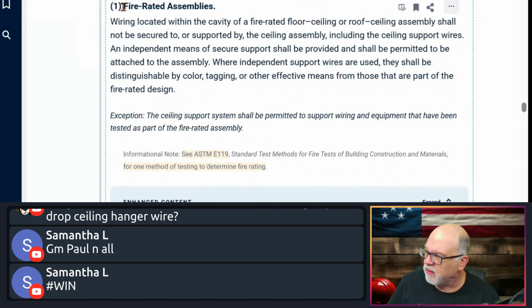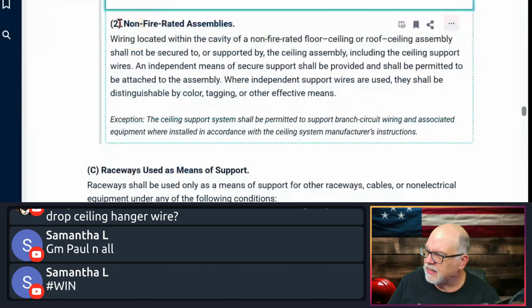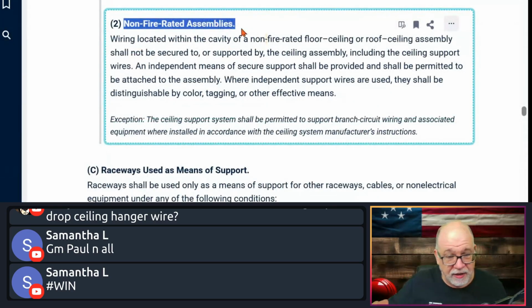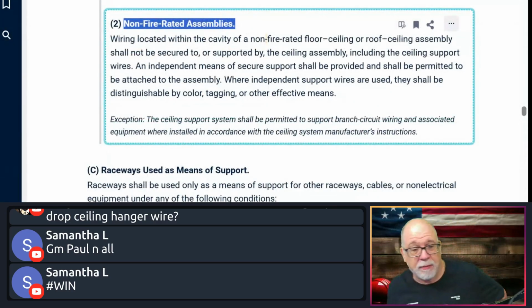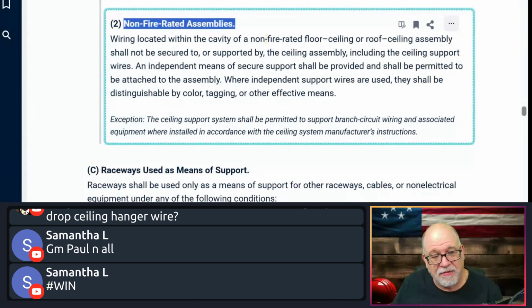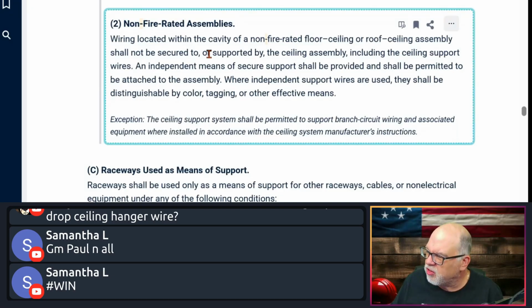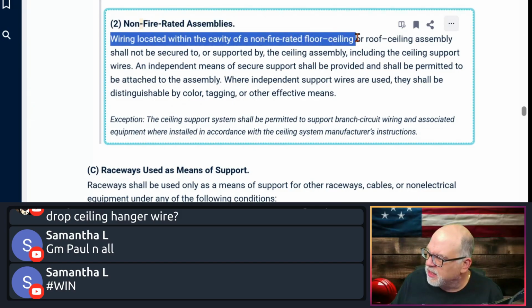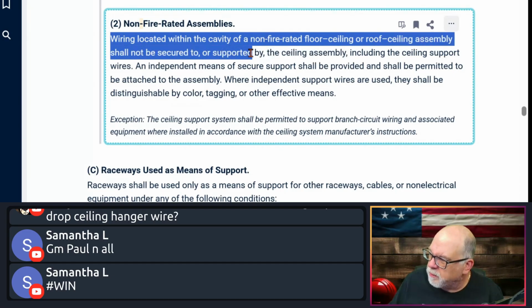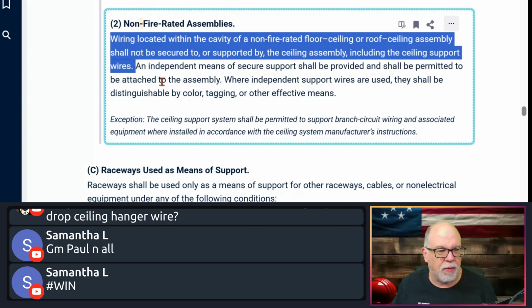Now, when you get into this, if it's a fire rated assembly, and 9 times out of 10 we're not dealing with a fire rated drop ceiling, which again typically has extra weight on it and is evaluated, some of those manufacturers may give some guidance and say certain things can be supported by their support wires. But in general, let's talk about the non-fire rated assembly. Wires located within a cavity of a non-fire rated floor-ceiling or roof-ceiling assembly shall not be secured to or supported by the ceiling assembly, including the ceiling support wires. There you go, Paul, right there.